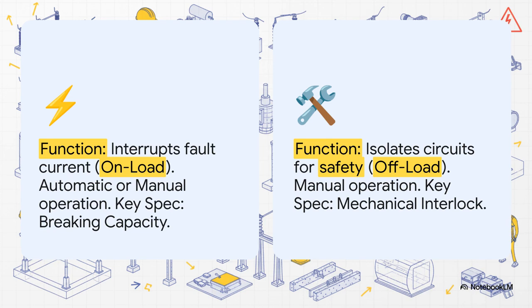And this slide just nails the difference. It's a super common and incredibly dangerous point of confusion out on site. A circuit breaker is built to work on load. It's designed to break a live circuit with huge amounts of current. An isolator is strictly offload. You only ever operate it after the circuit breaker has already done its job and killed the power. Mixing these two up is a recipe for a very, very bad day.